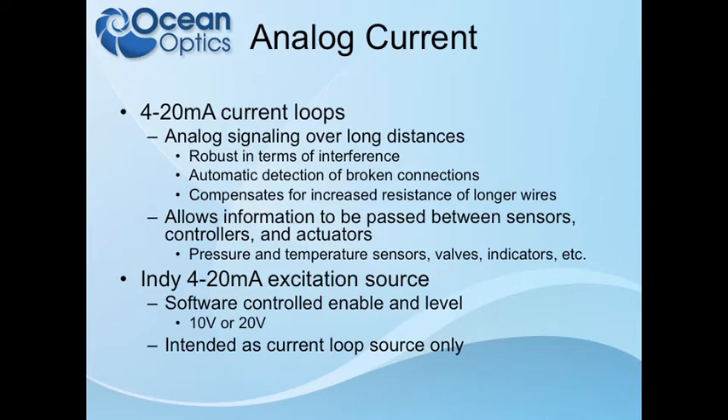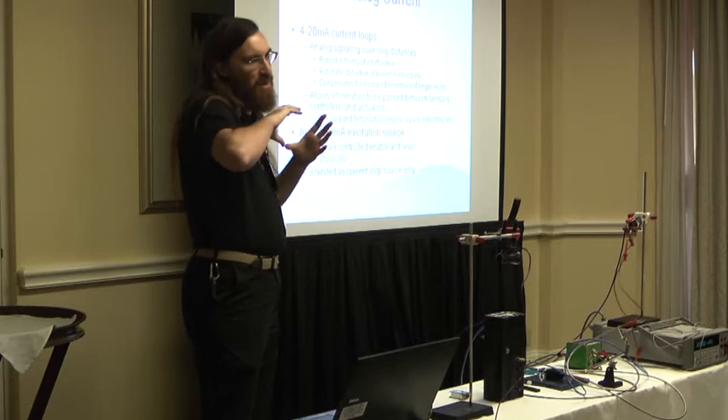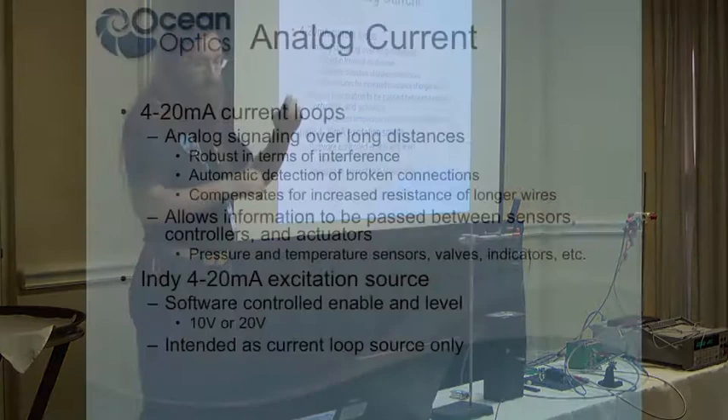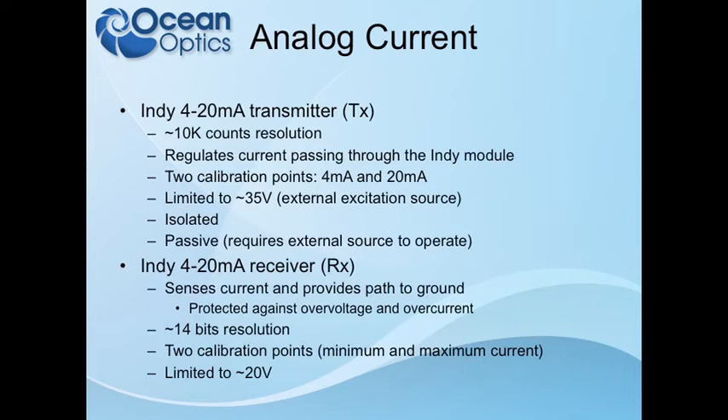The Indy can be a transmitter or a receiver. For any of these loops, you have to have an excitation source — something injecting power into the system so the current comes from somewhere, and all the current transmitted has to return back to ground at that excitation source. The excitation source on the Jazz is only intended as a current loop source, so it doesn't give you a general-purpose 20-volt power supply. The Indy has a 4 to 20 milliamp transmitter: if you provide an excitation source, it can vary the amount of current passing through to transmit information at some level between minimum and maximum.